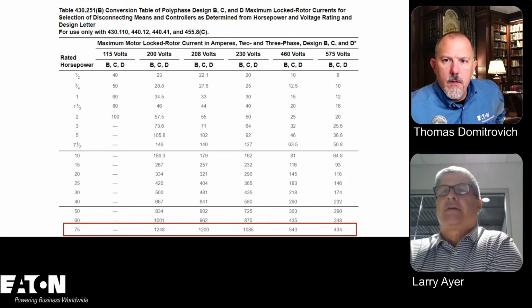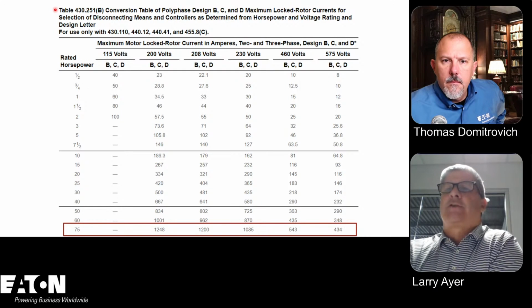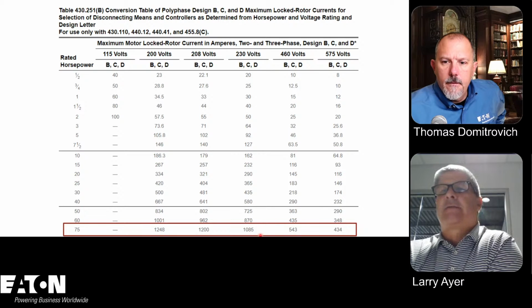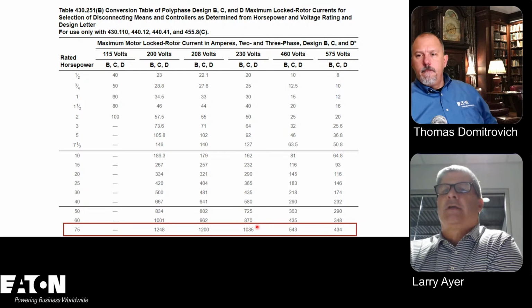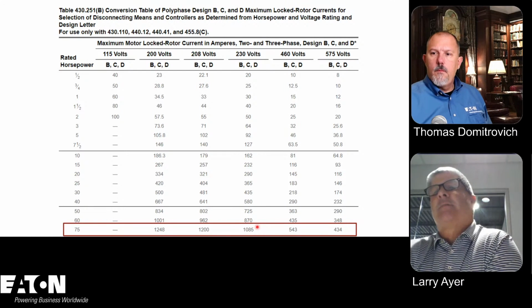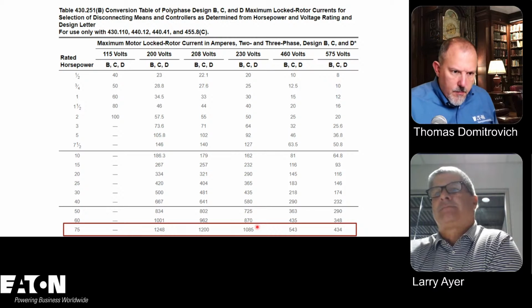Now this one's a little different. This doesn't say code. This says design B, C, or D. This is taken out of Table 430. And if you go to the 230 volt column for 75 horsepower, it still says 1085. So you can see they match, so you can use either method. You know that you have to put in something above that locked rotor current, 1085. Good point. Good point.